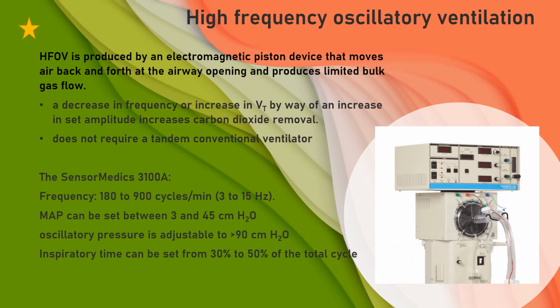On the mean airway pressure, we start at a setting of 20 to 25 cms of water. Starting at 2 cm higher than the baby's current conventional settings is usually the normal setting on the HFOV. Your clinician will also perform an escalating recruitment maneuver, which is an increase in the settings until an acceptable saturation is reached.